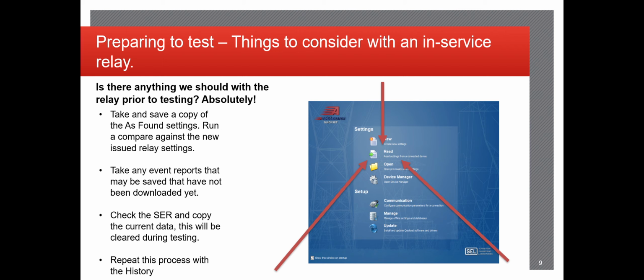You also want to take an events report file. An events report is anything that the relay may have done while it was in service, meaning if there was a fault somewhere in the relay protection scheme and the relay operated specific outputs or sent commands or signals to other relays, it'll show up in that event report. And you also want to provide that to the client too, to kind of cover yourself, because in case something were to happen during testing, you can show this to the client and say, hey, it wasn't me. You can see the events report that I have right now matches with what I showed up with, so something else happened during testing that wasn't directly affected by us.